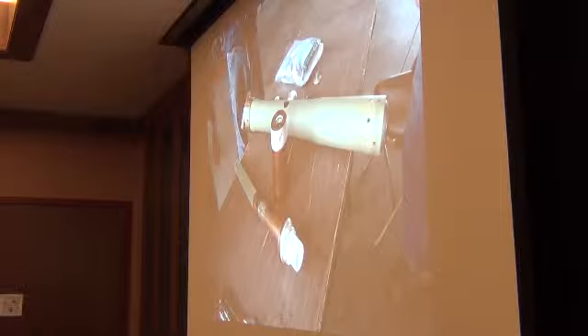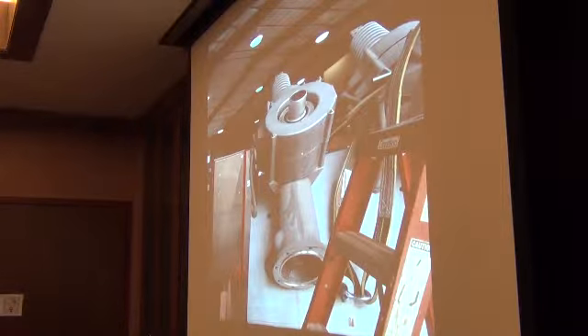And this is part of that internal mechanism. Right up here is where it actually mates up in the bushing. That's where the actual contact's made, and that's where the arc is broken. It has that SF6 gas in there, and this portion right here goes up into this tube, and then goes up right in here, and it all makes up right here. So power comes in through this bushing and out that one, and all the hot spots are right in the middle. Well, we were able to fix that, look everything over, recondition anything we needed to, the motor or pump or whatever it was for the air, and test. It tested well, so we're able to put that back in stock and have a spare ready to go in case we have that problem or another problem.